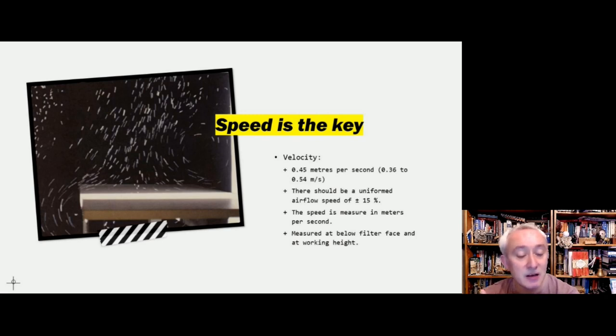And we measure the speed in meters per second, and we assess that below the filter face, around six inches, and then at the working height. And working height is defined as a space just above vials.